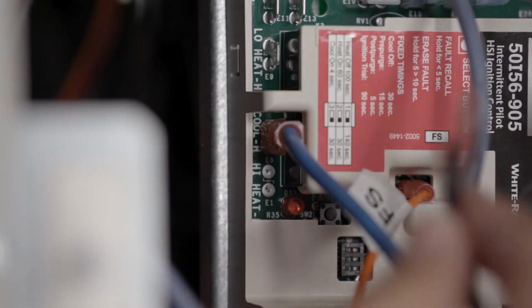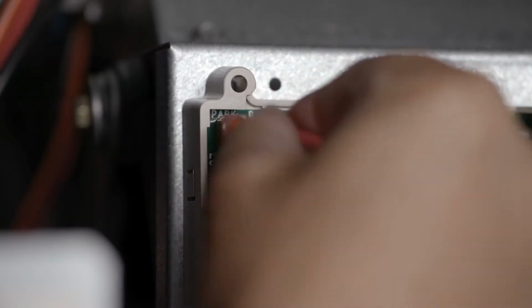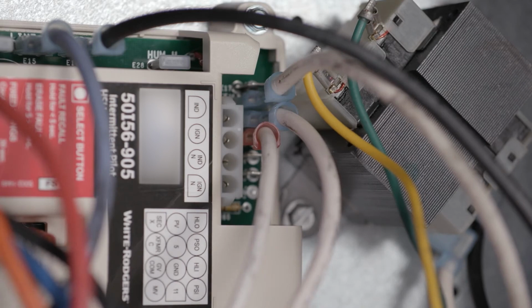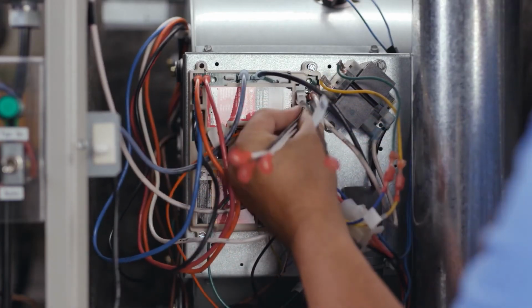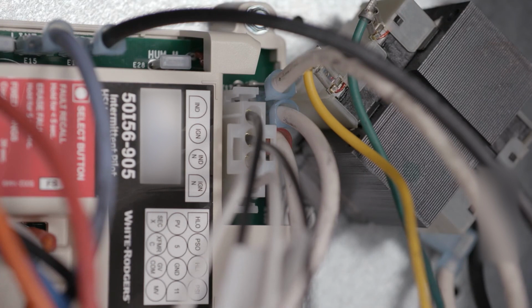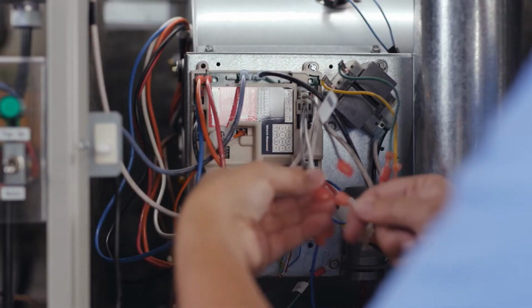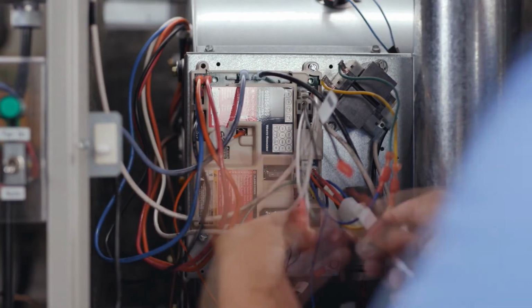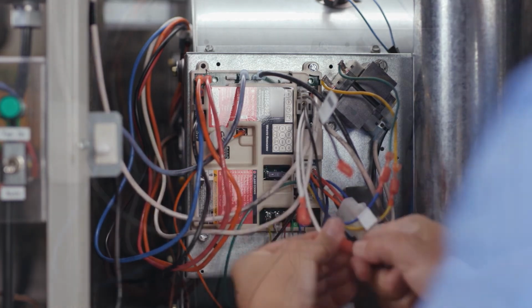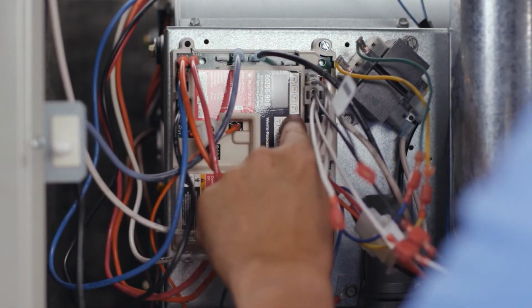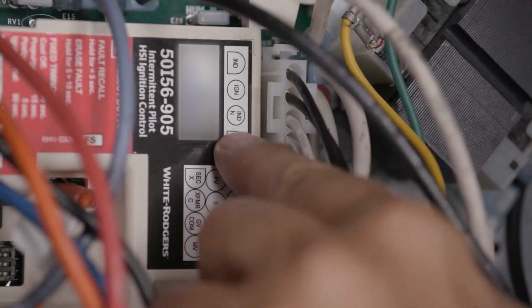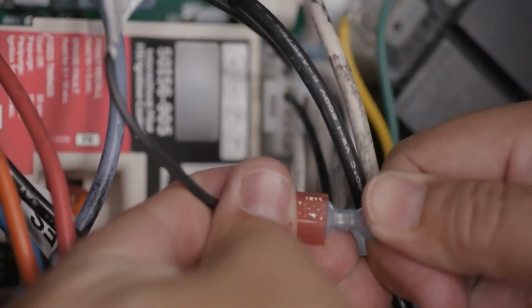Connect the blower motor leads. Connect the cool speed to cool-H, the heat speed to LO heat-H, and park unused leads on the park terminals. Connect the blower neutral to a line neutral terminal. Next, plug the 4-pin igniter inducer C harness into the control board connector E25. Connect the igniter 120-volt hot and neutral spades from the pilot assembly extension harness to the C harness igniter leads. Connect the inducer 120-volt hot and neutral to the C harness inducer leads.